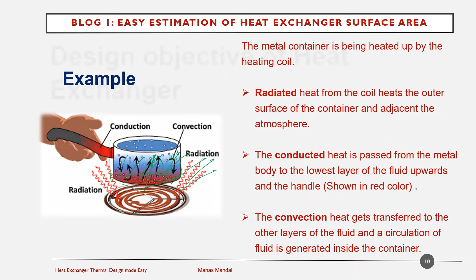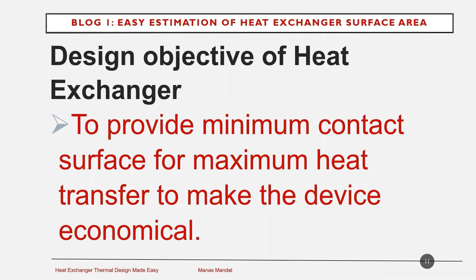The design objective of a heat exchanger is to provide minimum contact surface for maximum heat transfer to make the device economical. In most applications, the fluids do not mix with each other, but heat is transferred through a separating wall that takes on a wide variety of geometry. But there are some where fluids mix while transferring heat from one to another. In general, heat exchangers can be of two types: recuperator type or direct contact heat exchanger.